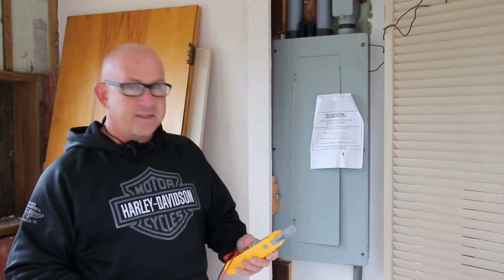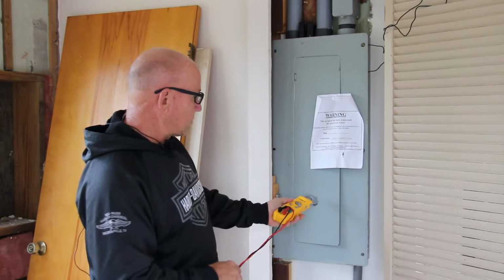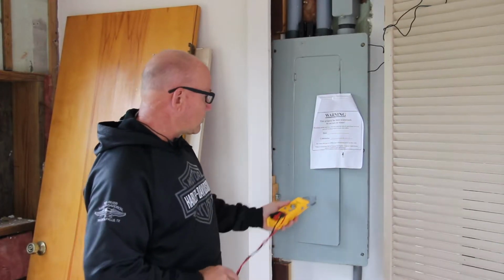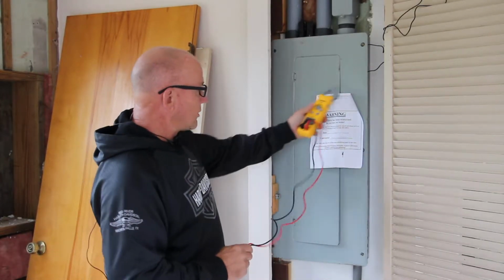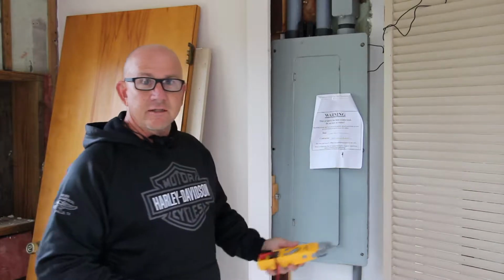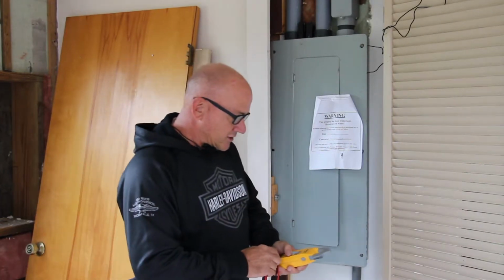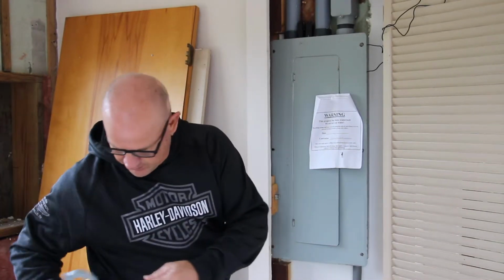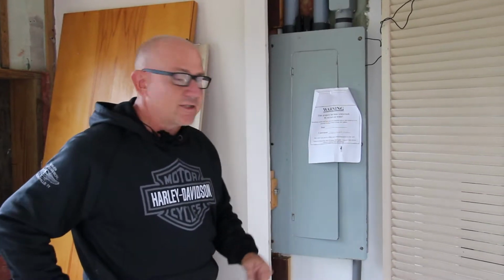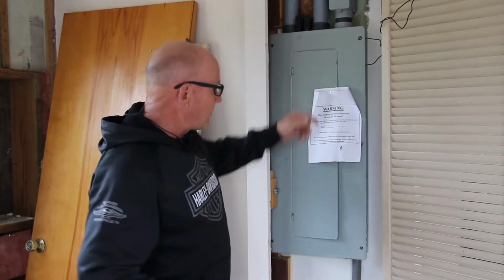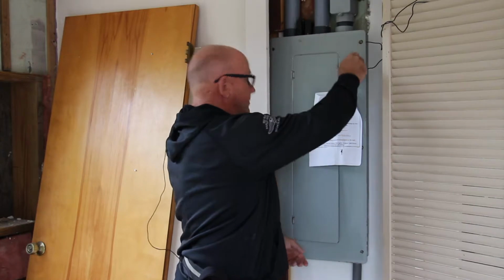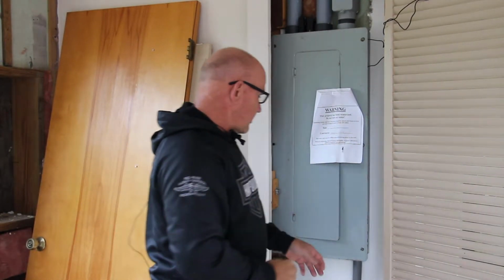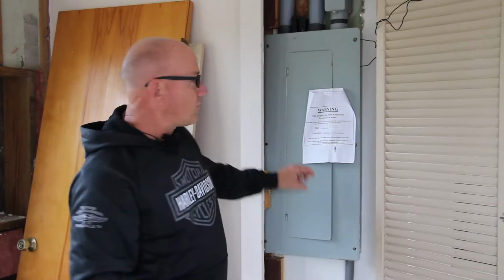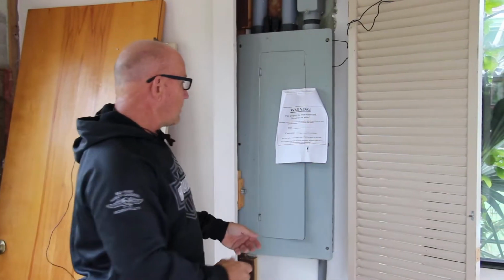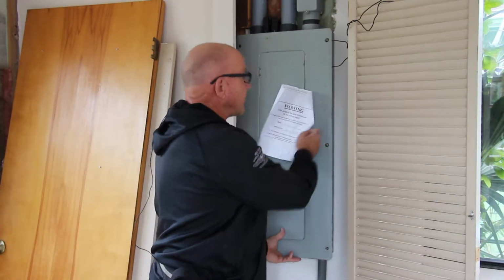It has a non-contact voltage detector on it. So before we touch the electrical panels, we want to run our meter around there and make sure that it's not hot, so that we can safely take the cover off. Once we do that, we'll take the screws out. We want to be looking at what kind of screws are fastened in here. Make sure they're not sharp pointed, make sure they're correct screws. This particular electrical panel is already missing a lot of screws, but we're going to go ahead and take the cover off now.